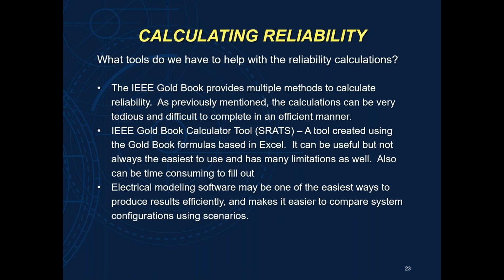Well, now in recent years, we have a third tool that is making our lives much easier when it comes to calculating reliability, which is electrical modeling software. Okay, we use electrical modeling software in a lot of applications for short circuit calculations, arc flash, load flow calculations, and that sort of thing. Not only for efficiency of your system and calculations for capacity, but also for safety.